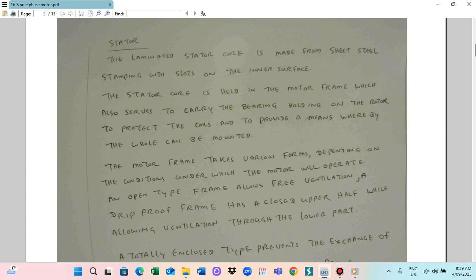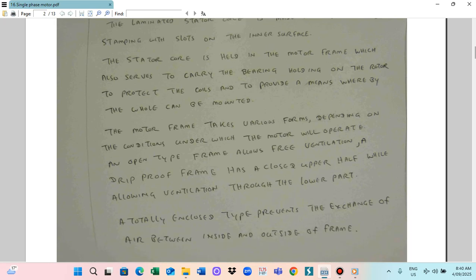The motor frame can take various forms. Some will be drip proof type, which means water cannot come inside and it can also ventilate, and the totally enclosed type prevents the exchange of air between the inside and outside of the frame. This depends on where you use the motor. If you use it at home, it is not too much of a problem. But if you use it in a very corrosive place, the motor should be totally enclosed. For the workplace or industry, such as the refrigeration industry, the motor should be drip proof. Some motors are underwater motors, totally immersed, so these should be totally enclosed. Depending on the place of application, the appropriate kind of motor frame should be utilized.